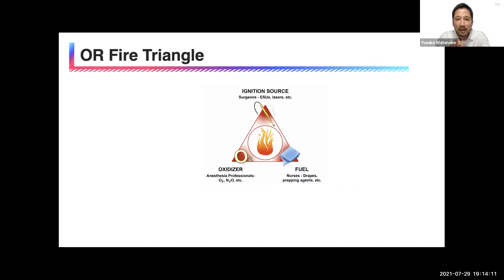Electrosurgical devices should never be activated when the active electrode is out of the field; it should be kept in its holster, and never be placed on the patient's chest, face, or groin areas. Light cables should be connected before the source is activated, and should subsequently be placed on standby before disconnection or placing the scope onto the surgical drape.